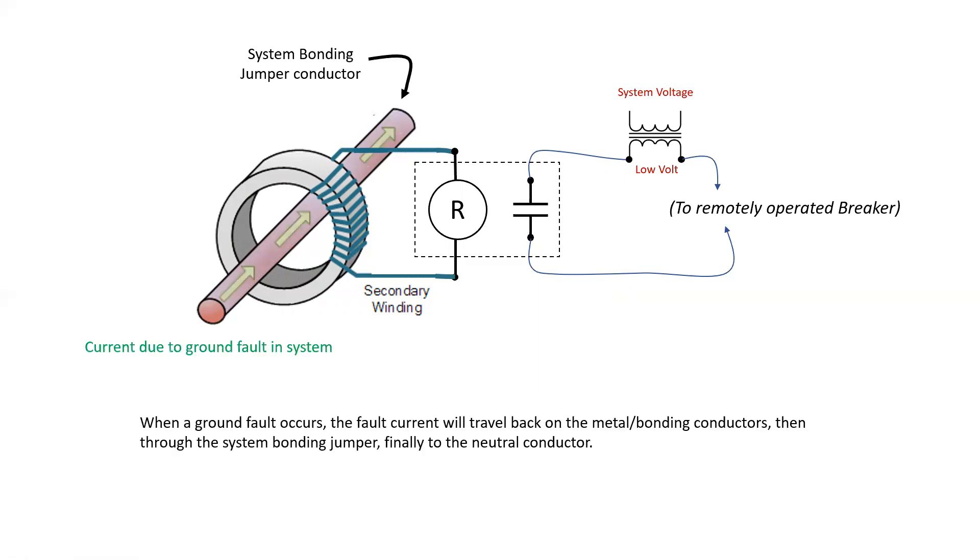During normal operation, there should be little to no current on the system bonding jumper and CT secondary. When we have a significant ground fault or a value that is above what our rating is, the fault current will travel back on the metal bonding conductors through the system bonding jumper finally to the neutral. And what that will cause is a value of current to flow in the secondary of our CT.